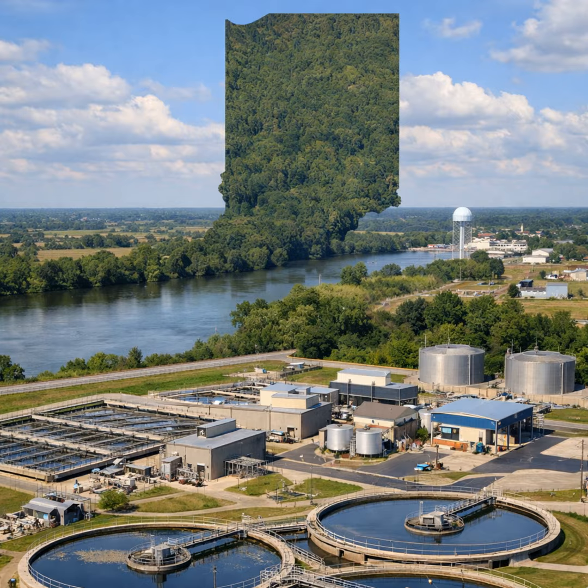MCRT in days equals total suspended solids in activated sludge process in pounds divided by the total suspended solids removed from the process in pounds per day. Or MCRT in days equals the total suspended solids in activated sludge process in kilograms divided by the total suspended solids removed from the process in kilograms per day.